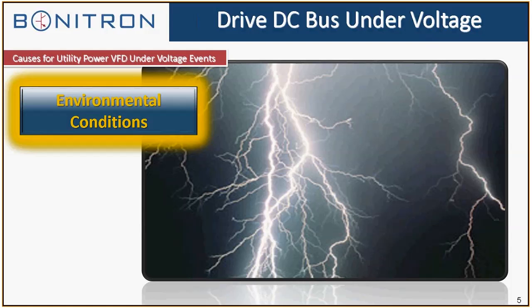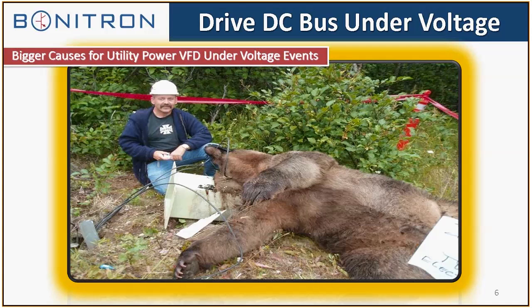So you're going to be dealing with the utility power events that that particular customer is dealing with, or internal plant events too, with the UPD products being a process level solution as opposed to something like a plant-wide UPS or distribution point UPS. Usually the process level ride-through is another level of redundancy for the distribution point UPS or distribution point backup. Even though you back up for the utility power events, you still could have internal plant issues. But basically we're dealing with environmental issues that take out your AC line, the utility power that's feeding the drives.